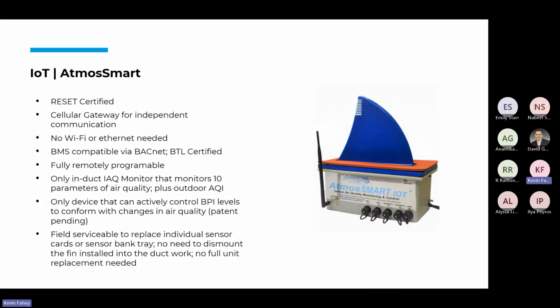And then the third sensor type is, as I mentioned, in duct. We put it in the return duct, generally just before the air handler, sometimes even in the mixing plenum of an air handler. So it's sourcing the air coming out of the space, and this also is connected with the ion generators. So based on the air quality that's coming out of the space, it can modulate and control the ions being generated into the space. So if you have heavy contaminant levels, you'll generate more ions, and if it's not so bad, then you'll generate less ions. So this is something that is integrated with the ion generators.